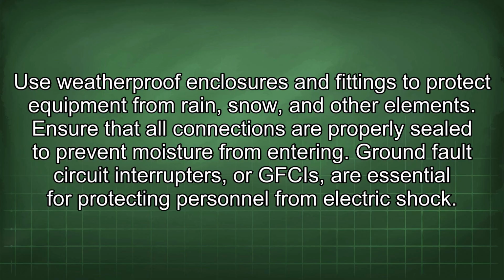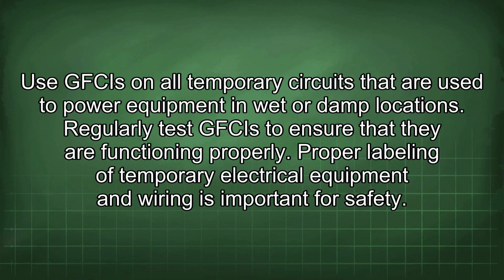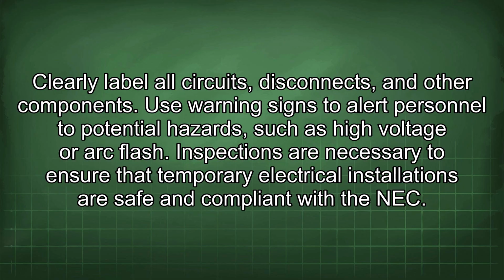Ground fault circuit interrupters, or GFCIs, are essential for protecting personnel from electric shock. Use GFCIs on all temporary circuits that are used to power equipment in wet or damp locations. Regularly test GFCIs to ensure that they are functioning properly. Proper labeling of temporary electrical equipment and wiring is important for safety. Clearly label all circuits, disconnects, and other components. Use warning signs to alert personnel to potential hazards, such as high voltage or arc flash.